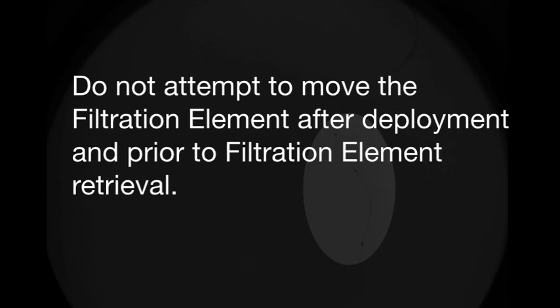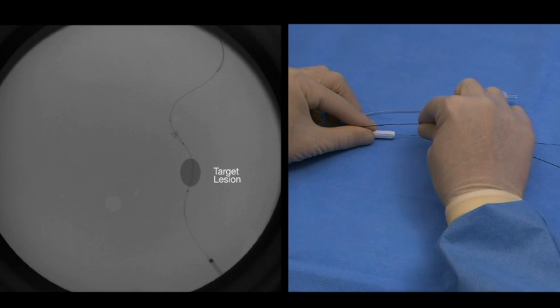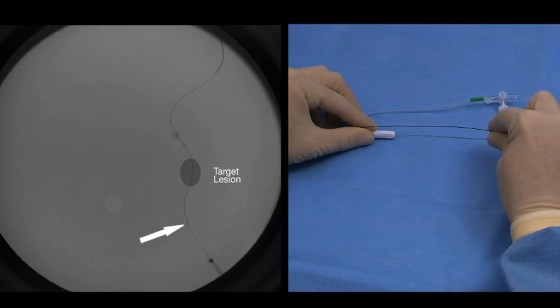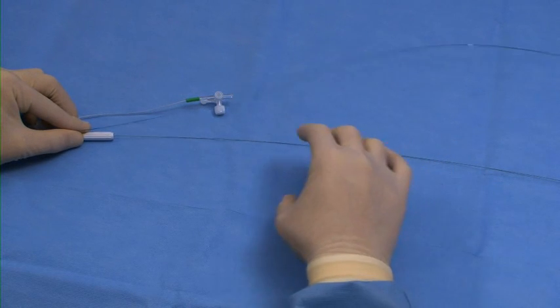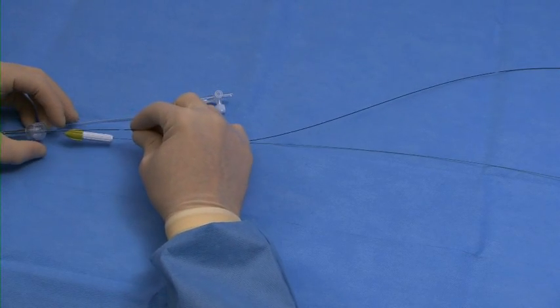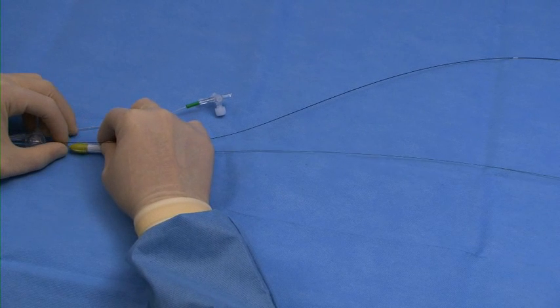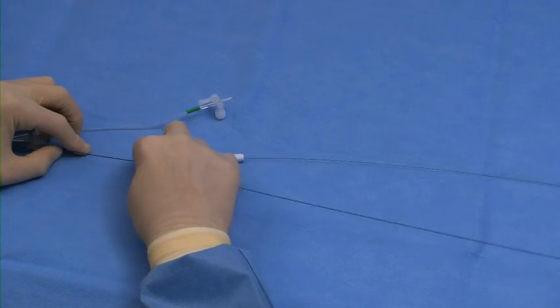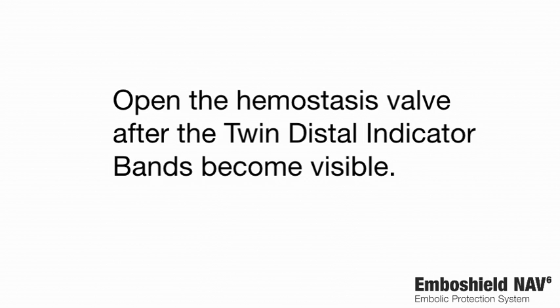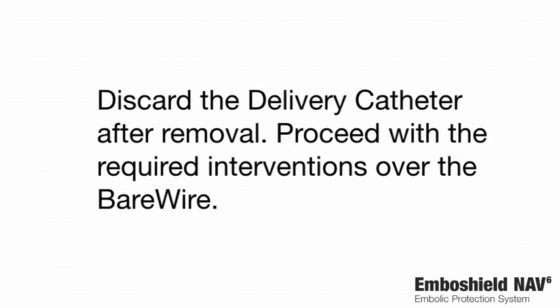Do not attempt to move the filtration element after deployment and prior to filtration element retrieval. Maintain bare wire position and remove the delivery catheter. Notice the single distal indicator band is positioned 15 centimeters from the rapid exchange exit port and the twin distal indicator bands are located 5 centimeters from the rapid exchange exit port to aid catheter retrieval. Open the hemostasis valve after the twin distal indicator bands become visible. Discard the delivery catheter after removal. Proceed with the required interventions over the bare wire.